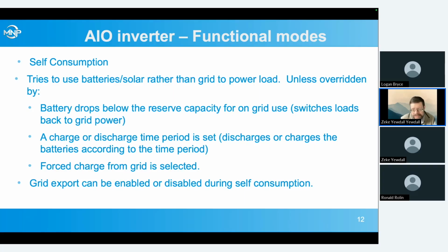Not all utilities are accepting this ability to limit the export. Some of them just base it off of the rating of the inverter or the rating of the PV array and don't really look at the ability of the inverter to limit that export, but it does have that ability, and if your utility will accept that, that is one of the settings that is only accessible by the installer levels, not the end user. So that qualifies for requiring a password and everything to change, and it's not accessible for the end user to just be changing that grid export. That's a requirement of some utilities for accepting that.